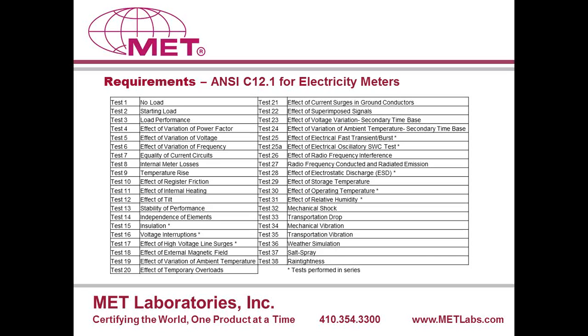The primary difference is that C12.20 has a tighter accuracy. So, for instance, if you have a meter that's a 0.2% accuracy class, that would be tested to the C12.20 standard, and in turn that standard references back to some of the criteria out of the 12.1 standard. There are some other things having to do with Blondel, non-Blondel, but essentially that's the difference between the two. And the tests, although some vary between the two standards, are pretty much what you see here with these 38 tests. So this is what our focus is in the laboratory.